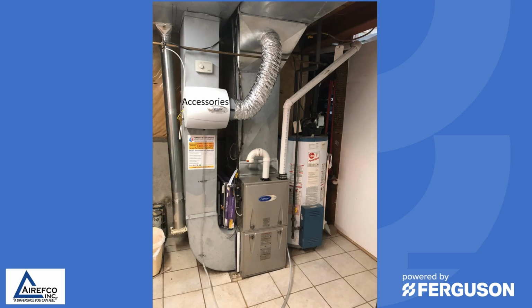I've always said that if a technician would take a picture of the furnace and the surrounding ductwork, I could probably diagnose and tell them what's wrong with the system without even going to the job site. So let's stand back and see what we can see. The first thing we observe would be the filters. Most homeowners tell you that they religiously change their filters, and we know that that's usually not true. Here's a telltale sign: extra filters sitting on top of the return air plenum. I wonder if the filter's been changed in the last month or so.